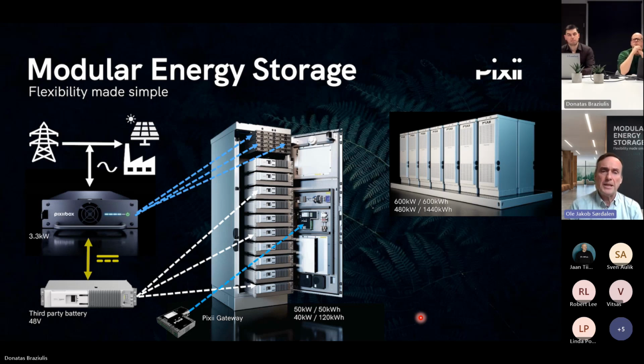We can scale up the capacity as required by putting a number of these boxes into a cabinet, as shown here. In this case, we have a fridge-size energy storage system, pre-wired, everything included, with batteries from third party and power converters - in this case 15 of those - making up a 50 kilowatt power conversion for charging and discharging, and depending on battery chemistry, 50 kilowatt hour.